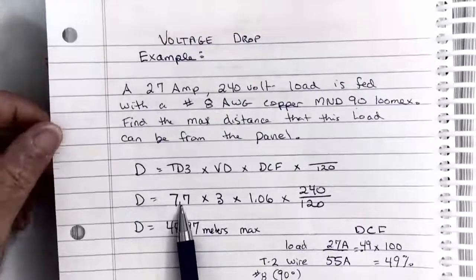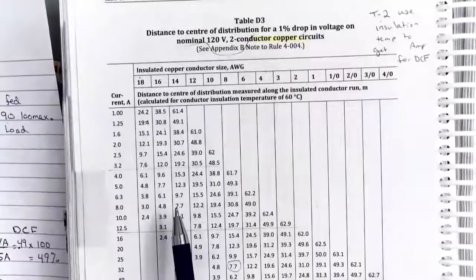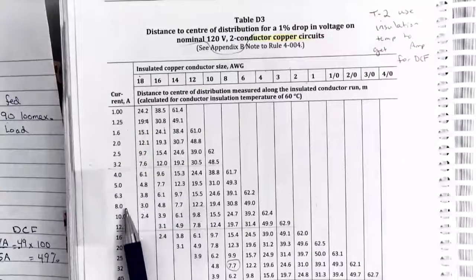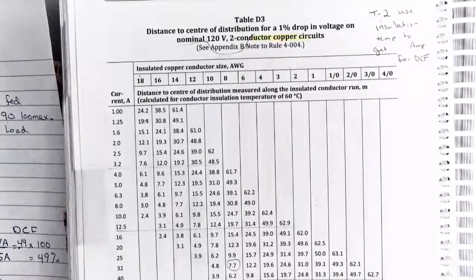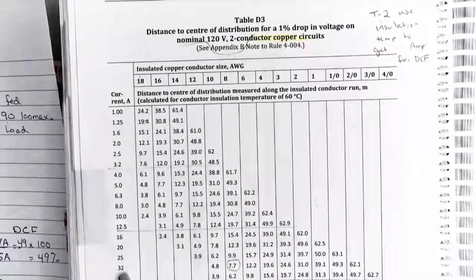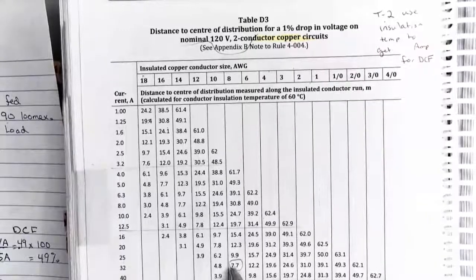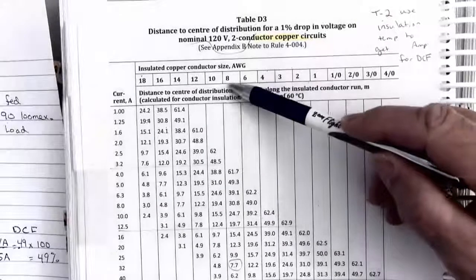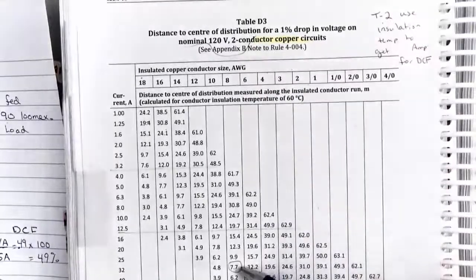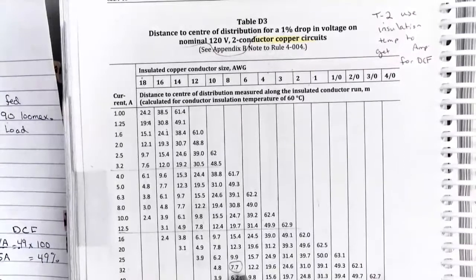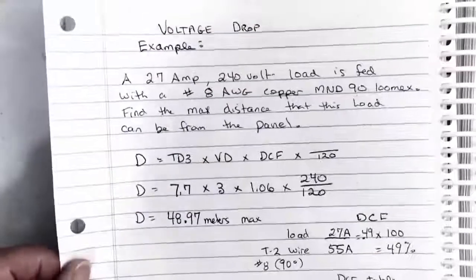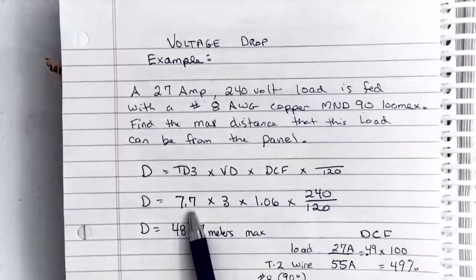So to find the distance from table D3, what we do is we know that we were given a 27 amp load. So running down the left hand side of table D3, I want to go to a number that's larger than 27. So my first choice is 32. And it told me that I was going to be using a number 8 conductor. And if you look up here, my number 8 conductor matches up with my 32 amp load. And this number here, the 7.7, is now what we call the meters one way that we're allowed to go, and it's our basic number from table D3. So remember 7.7, and that's what I put in here on table D3, 7.7.